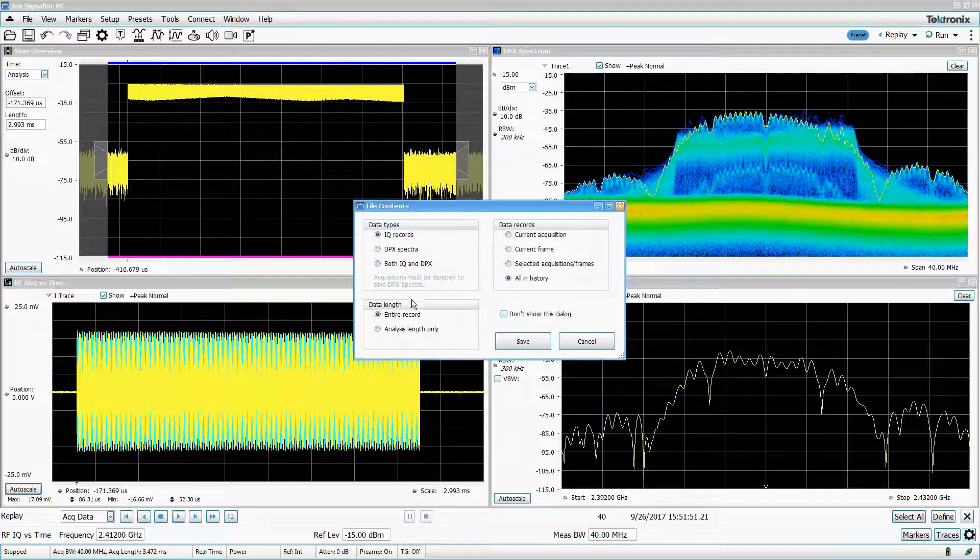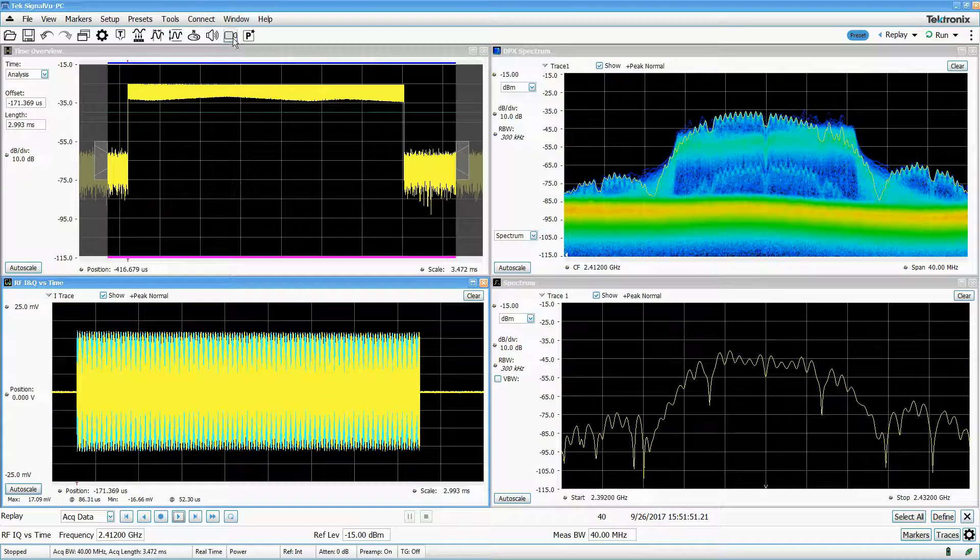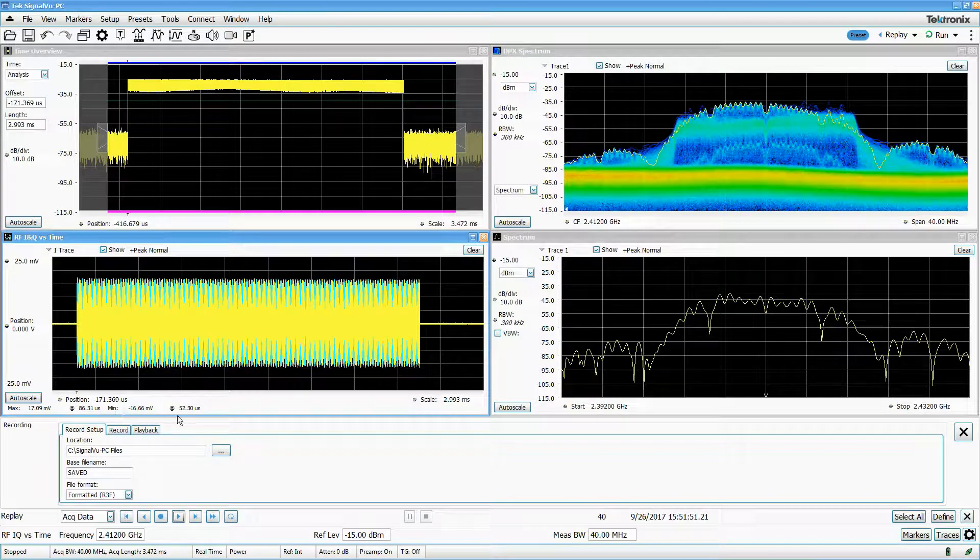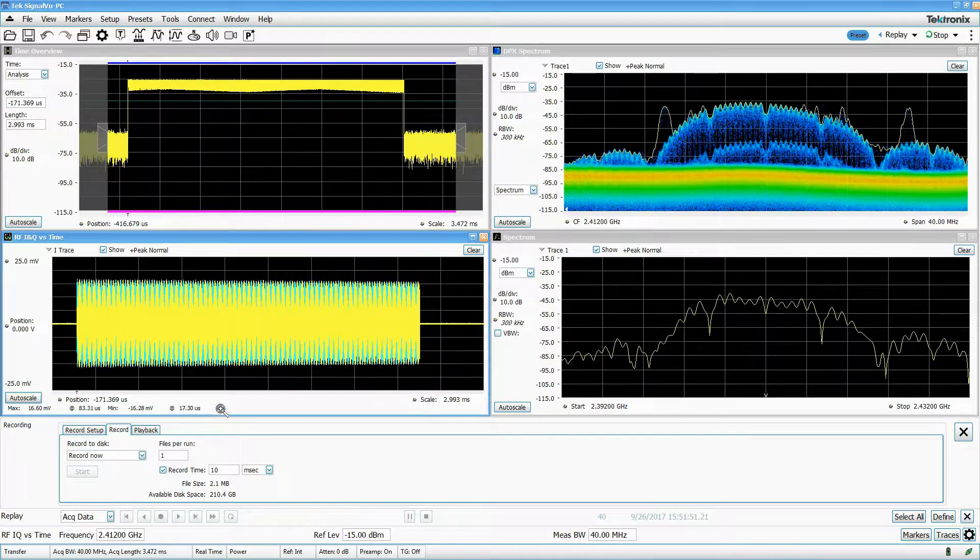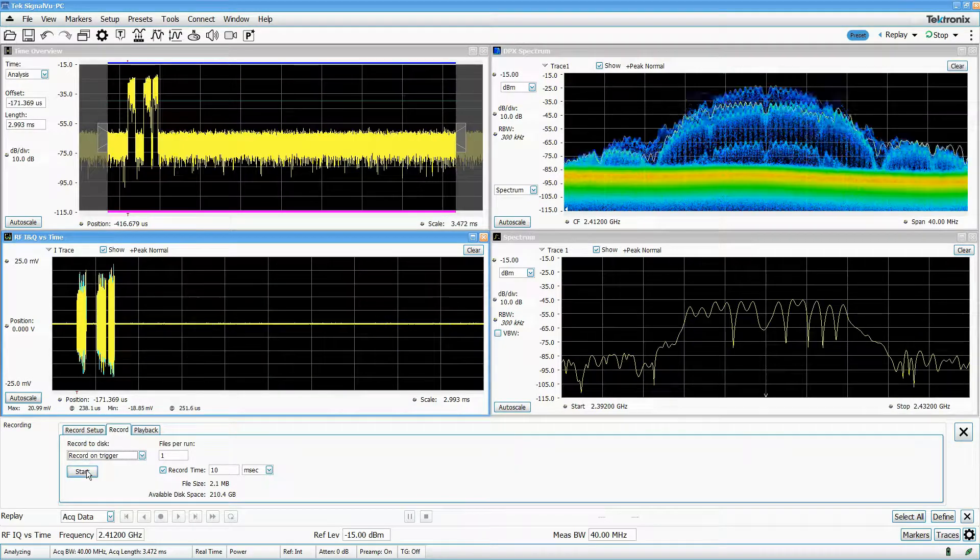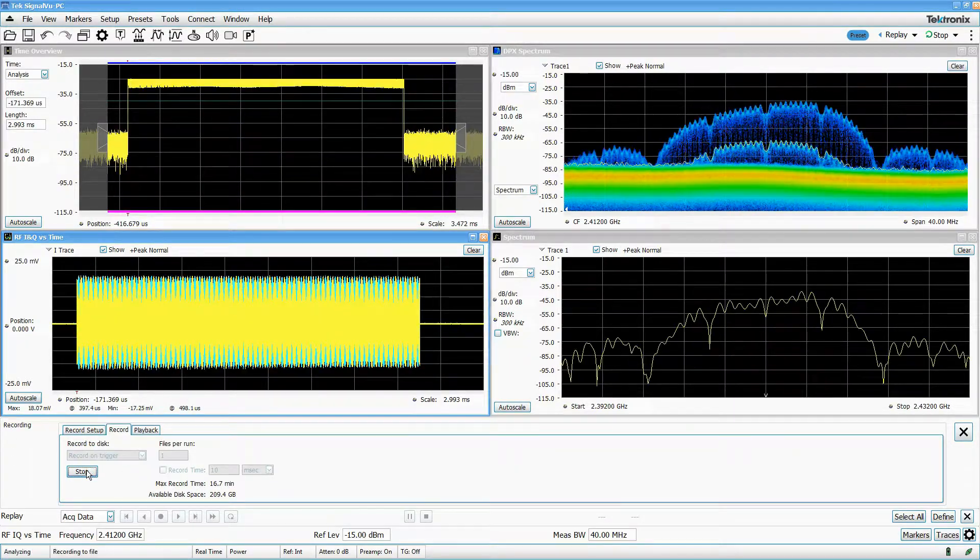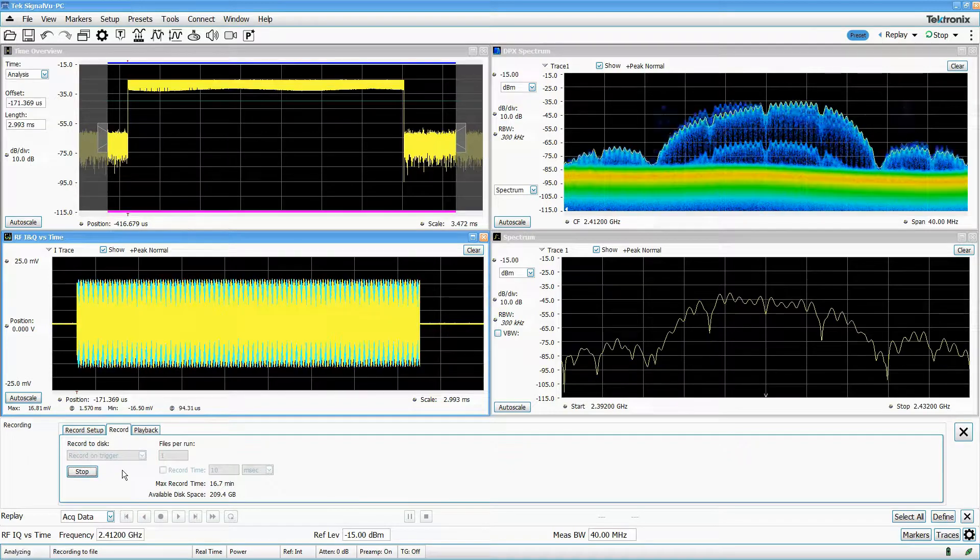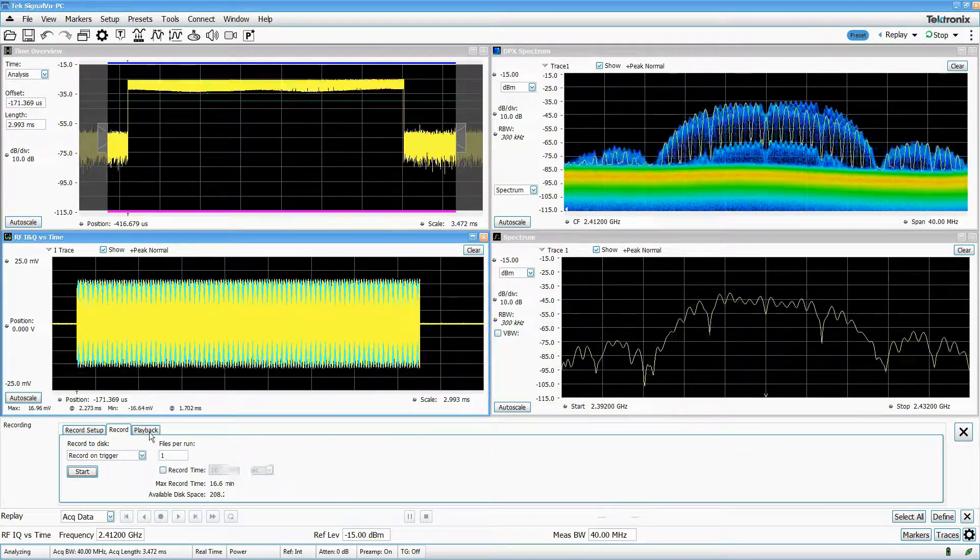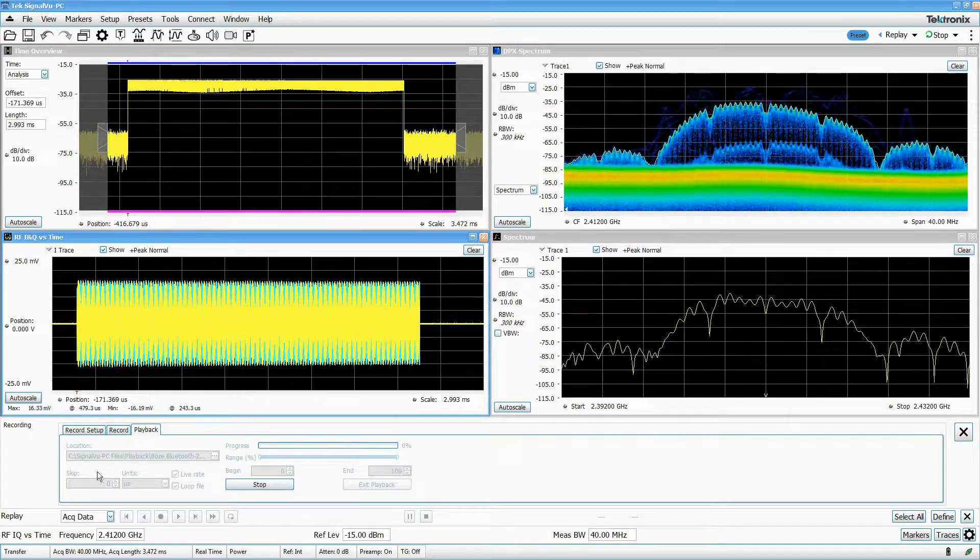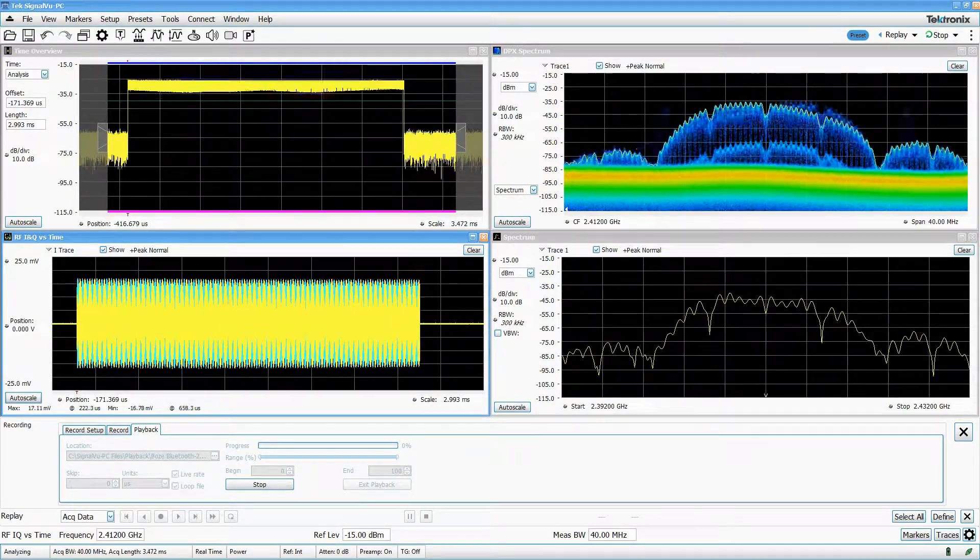SignalVu-PC also allows the streaming of contiguous IF data to a file. This use case captures a single long record of contiguous raw A-to-D converter samples. No measurements or corrections are made on this data. If you need to capture seamless data for a long period of time, this is the way to go. SignalVu-PC has a playback feature that reads in the streamed data file as if it was coming from an RSA, and allows you to make measurements on it as if it was newly acquired.